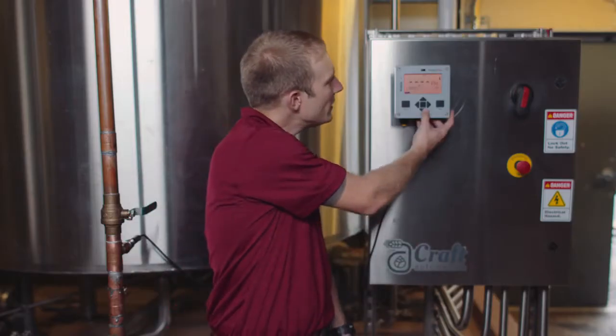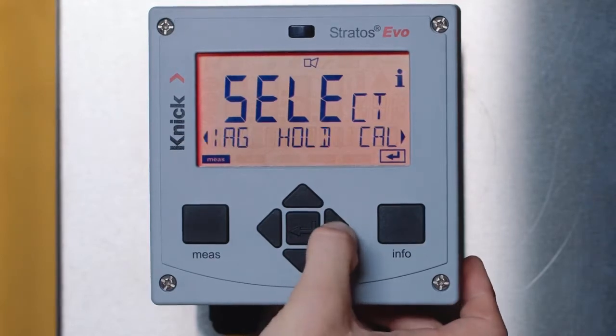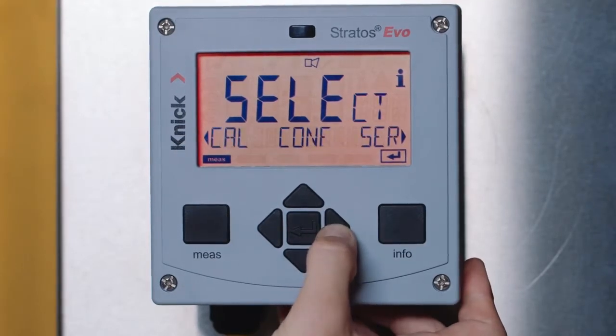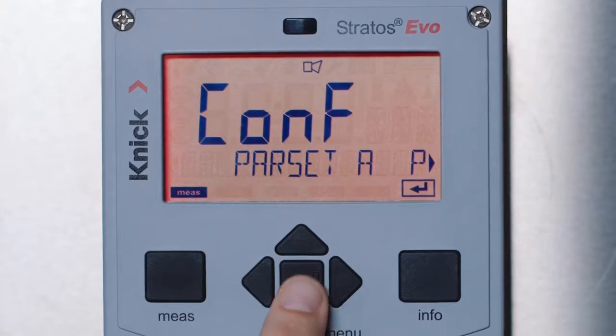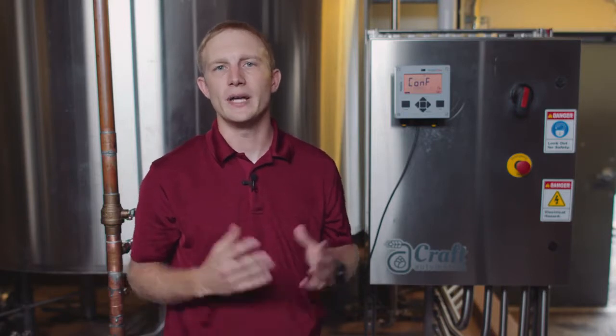First, press the menu button and then toggle to the right to configuration. Pressing enter, you will see the two parameter sets available. This allows you to program each parameter set to different measurement situations. This is useful, for instance, in batch processes, which may have different characteristics for each batch being run. The parameters can then be changed via an external input into the transmitter. We're going to configure parameter set A.